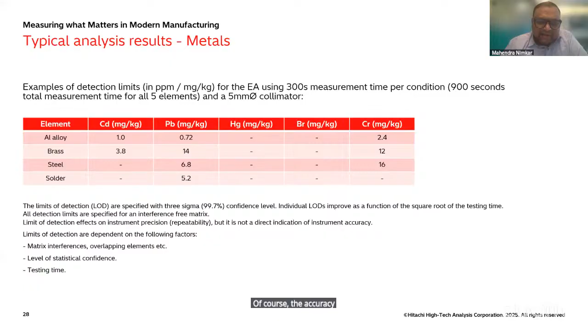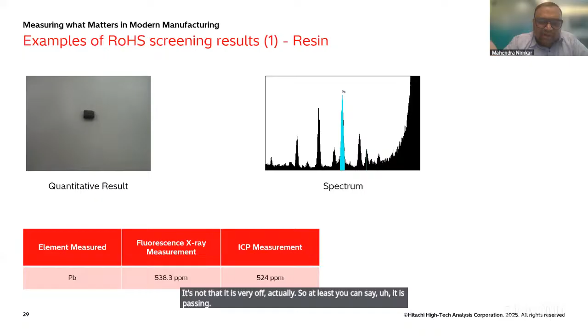So there are some examples here. We are checking one example, a resin. We have taken some photos. It's a small resin, and we are testing it, for example, for lead with XRF. It shows 538 ppm, and ICP shows 524. So it's very close, not very off at all. So at least you can say it is passing, because the requirement is 1000 ppm for RoHS pass or fail.